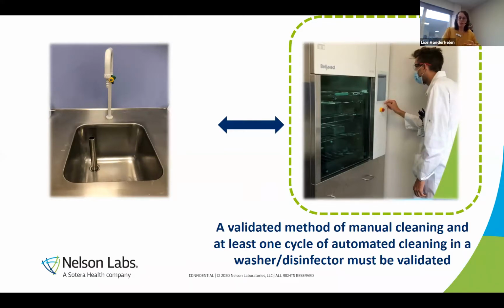You can add a manual cleaning because not in all healthcare facilities there is the availability of a washer disinfector, specifically when you think about reusable devices for dental applications. There, not every dentist practice has a washer disinfector. So, or the market where you're going to put your device, the hospitals do not generally have it because the budgets are lower. So things to consider, but if your device is compatible with an automated cleaning step, then you should at least validate that and ideally combined with a manual cleaning validation.